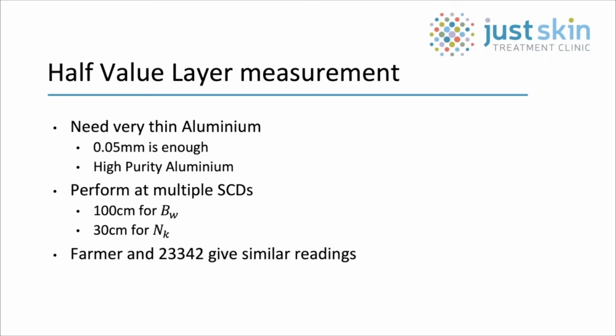The main challenge when performing these HVL measurements is that, like me, you probably don't have aluminium sheets thin enough. I bought a set of sheets with thicknesses from 1 millimeter down to 0.005 millimeters off AliExpress, which I measured the thickness of using a micrometer. My final results used a 0.05 millimeter sheet as the thinnest sheet and corrected the result using equation 5 in the Swiss recommendations.